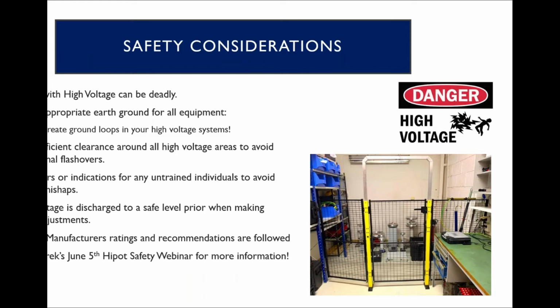So talking about those safety considerations, the safety of the operator and those around them should always be your highest priority. A few things to consider when working around high voltage is that anyone working with high voltage really must maintain a really healthy respect for the risks. Only personnel who have been appropriately trained should really be directly involved with working with high voltages. You really should make sure that you establish an appropriate ground, an earth ground, for all equipment involved with the high voltage process when it's required. You have to make sure that you don't introduce any ground loops into your high voltage system, as there are a lot of powers and voltages throughout the system that could cause issues with that.